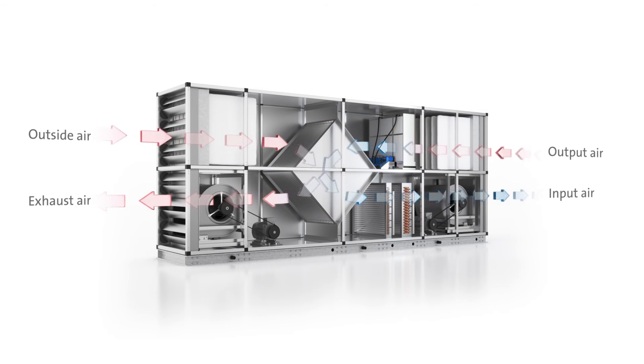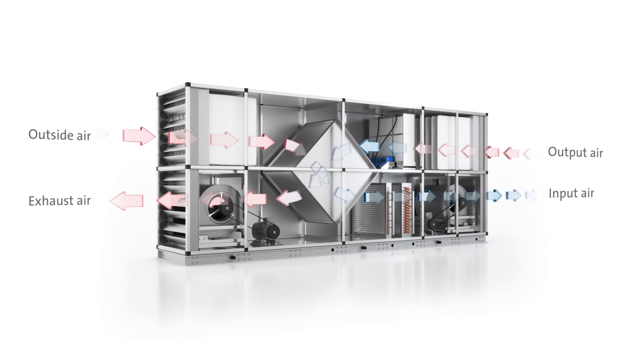Using an evaporative cooler allows to do without a cooling coil, or at least to reduce its size, and therefore its power consumption significantly. If correctly calculated, this leads to significant savings in operating costs.